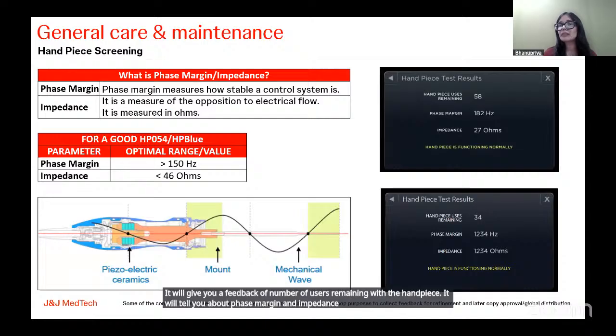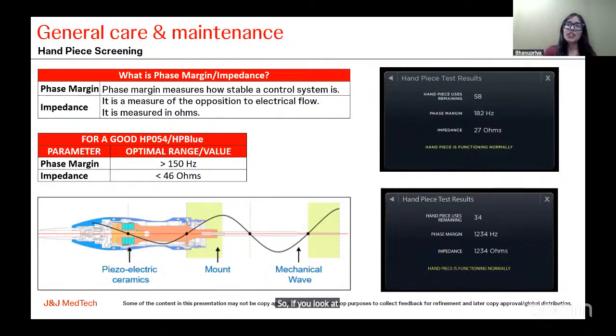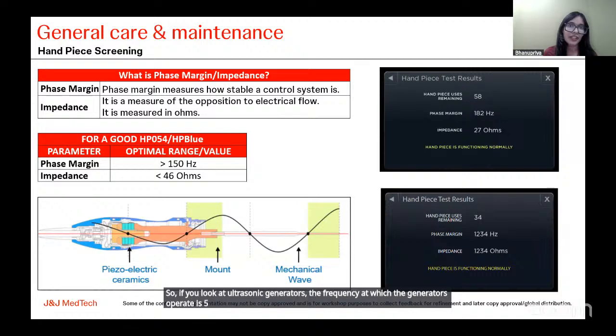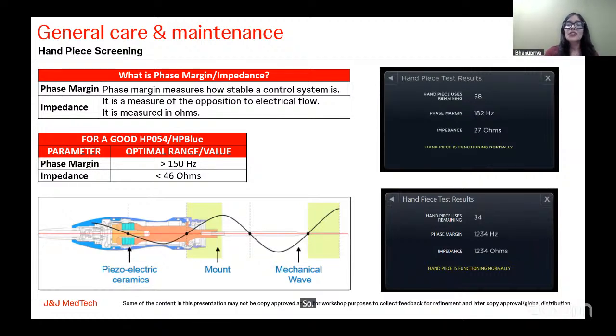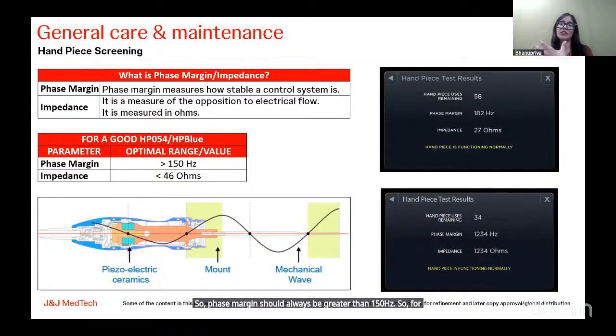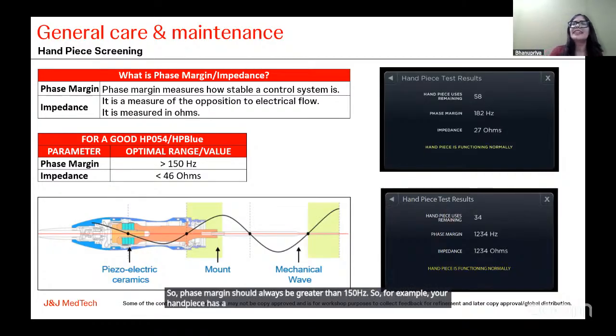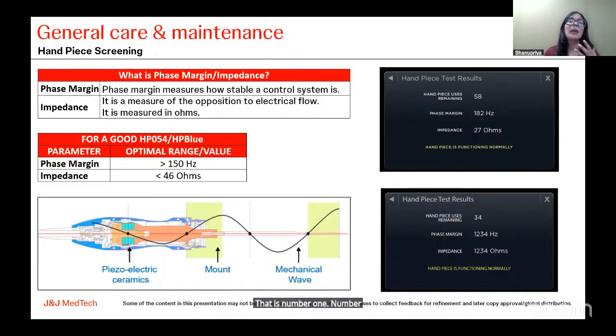Now, what is phase margin? What is impedance? If you look at ultrasonic generators, the frequency at which the generators operate is 55,000 hertz, right? So phase margin should always be greater than 150 hertz. So for example, if your handpiece has a phase margin less than 150 hertz, it means that it is unable to provide a frequency of 55,000 hertz. That is number one. Number two is impedance.